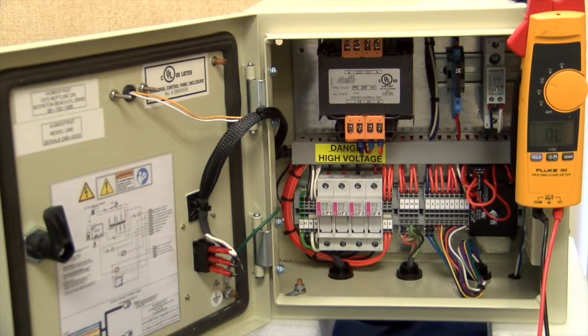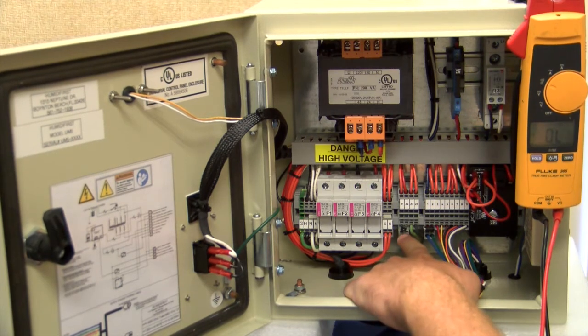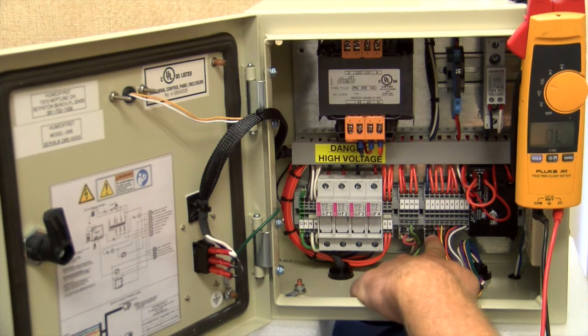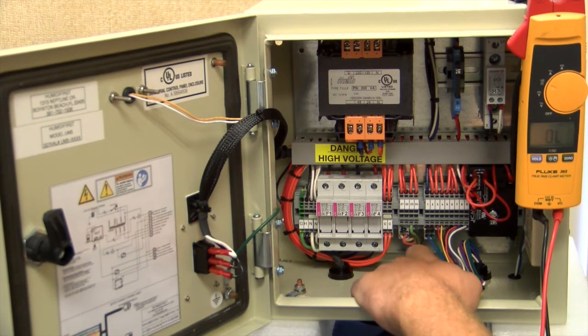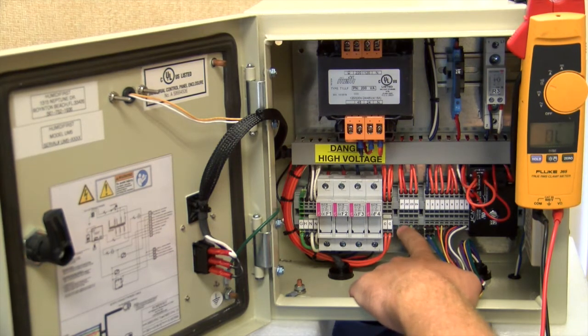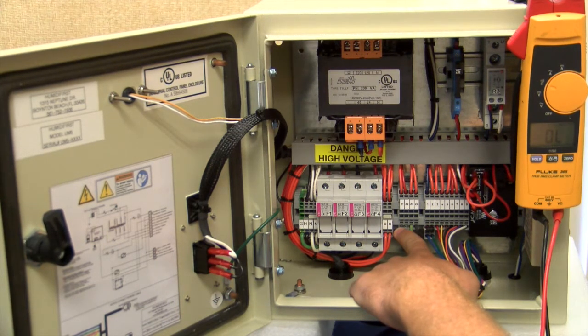We are now going to check your surge arresters. You have two surge arresters on this unit at 21, 22, and 1 and 2. Surge arresters work the exact opposite of a fuse. If you tone across it and don't get continuity, then it's good. If you tone across it and get continuity, it is bad.